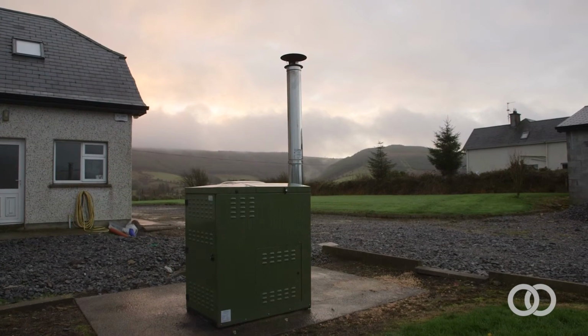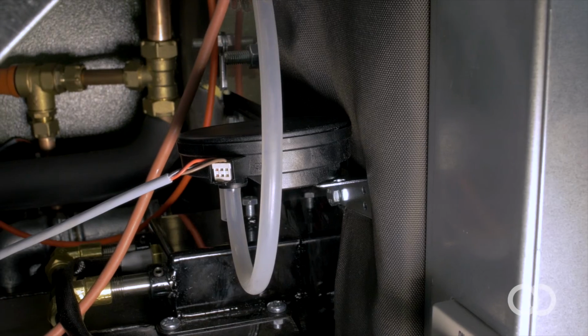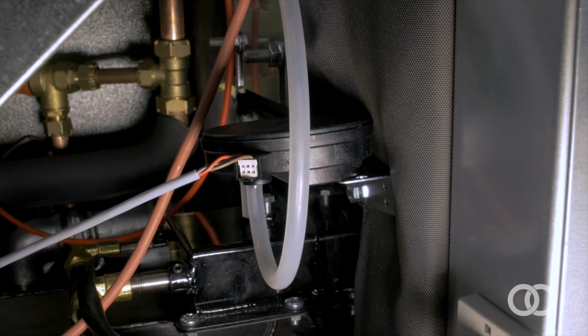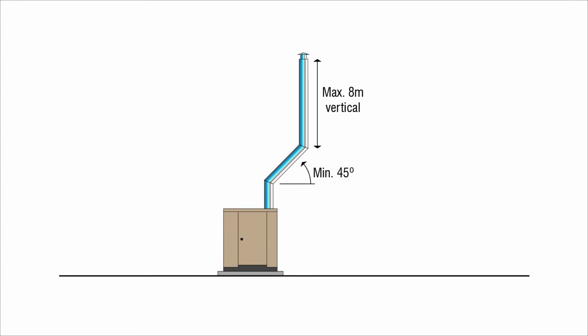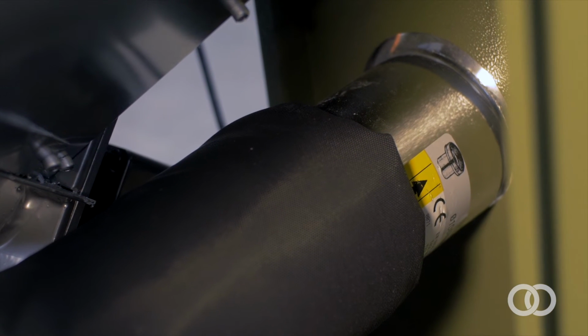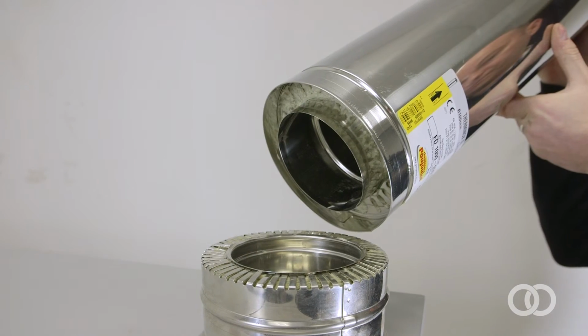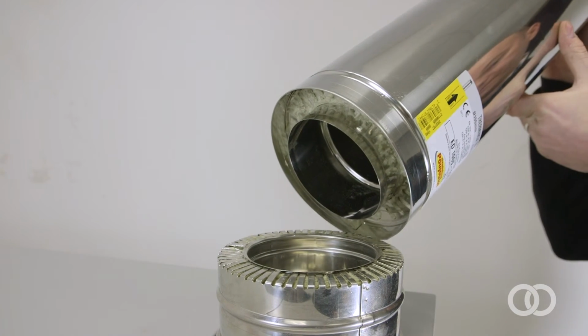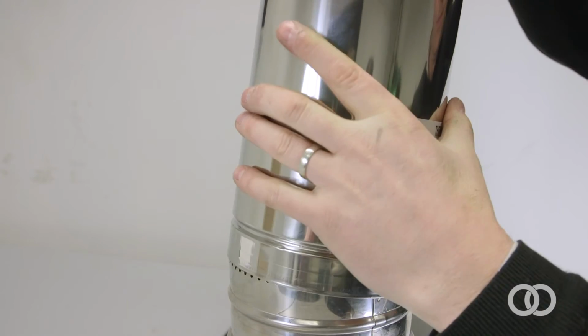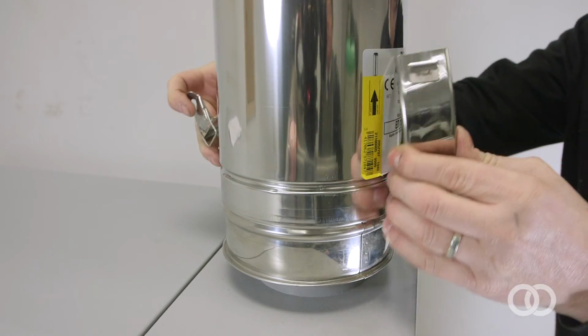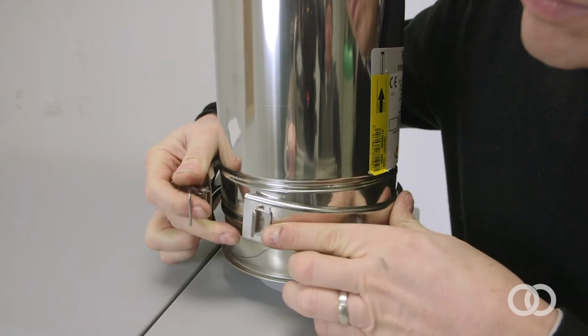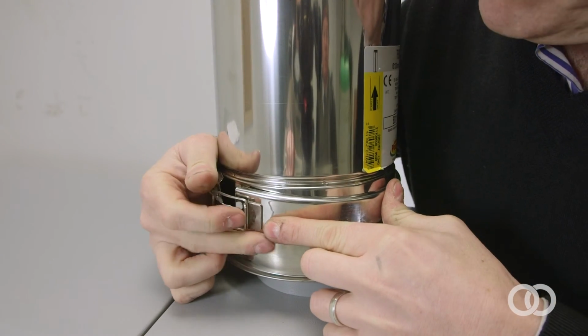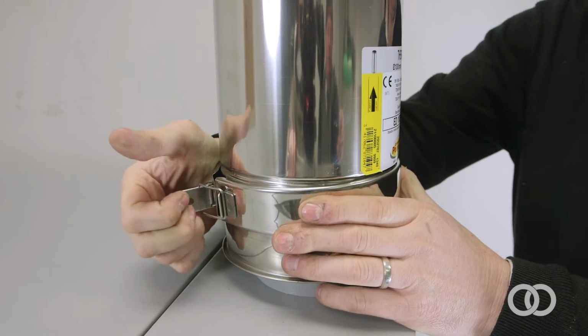Sometimes an anti-downdraft cowl or spinning cowl may be required. When commissioning, we will show you the importance of draft and how the vacuum regulator assists this. The flue pipe must not include any horizontal pipe runs. It is also advisable not to exceed 8 metres of vertical pipe. The W-Compact biomass boilers have an 80mm diameter transition pipe from the exhaust fan to the flue adapter. W-Compact boilers have been tested and approved with 4-inch 100mm twin-wall stainless steel insulated flue, so you will need an 80-100 adapter. The installer can also choose to use a 5-inch 125mm flue.